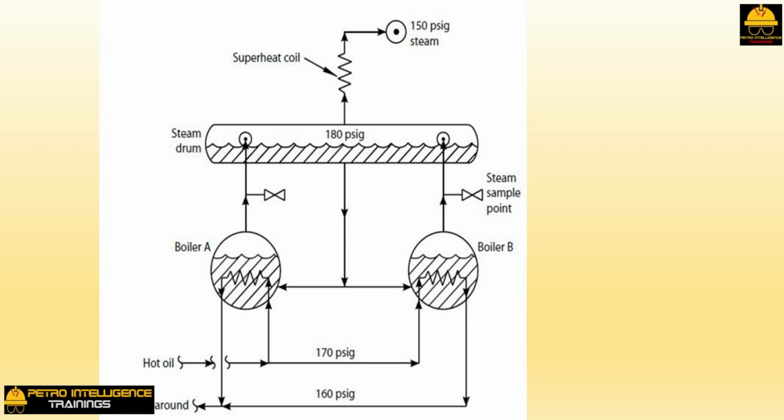This scenario was repeated 3 times, until the plant manager intervened and instructed the engineering department to purchase a new $250,000 tube bundle for boiler A. The refinery had lost $100,000 per day in production for about 40 days, up to the day that the new tube bundle arrived. The new bundle was quickly installed. As the gas oil pump around flow was restreamed, the flow of water into the fractionator was once again initiated.